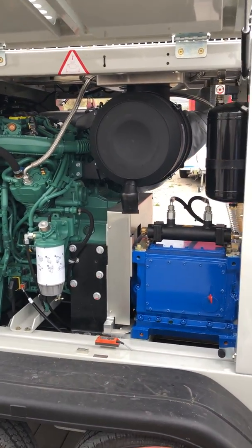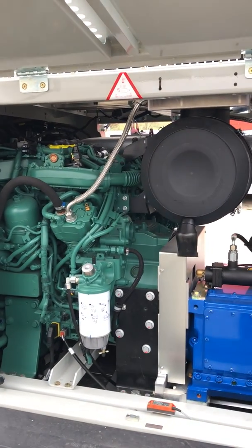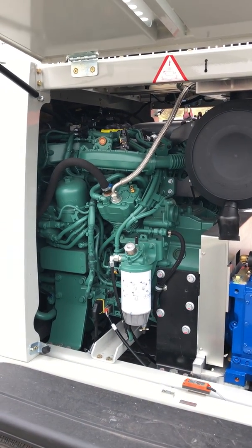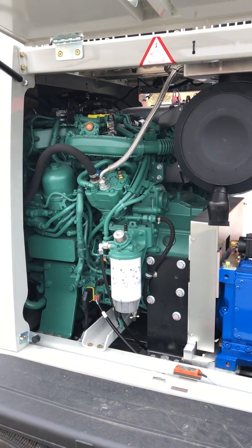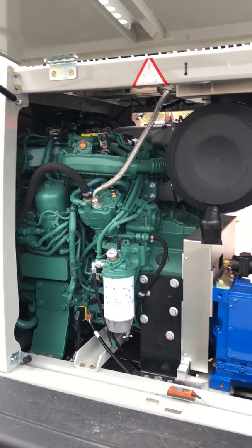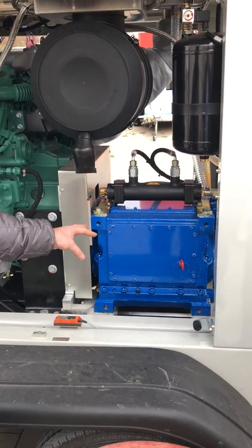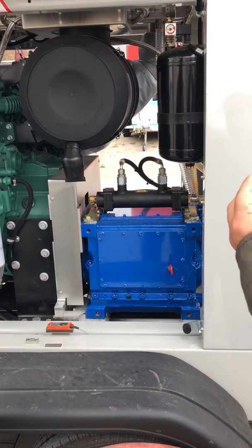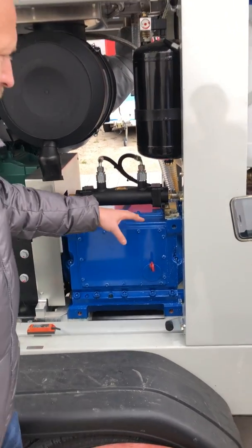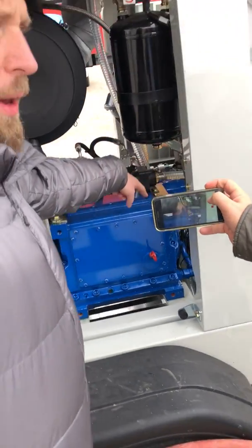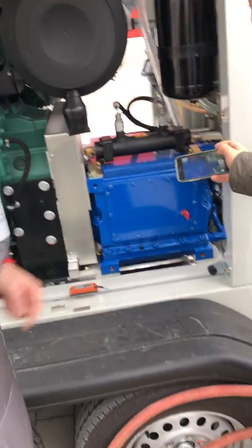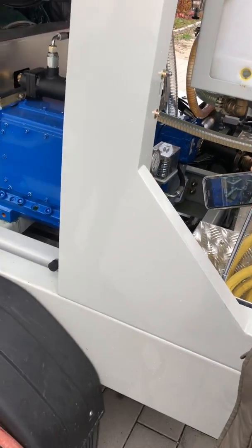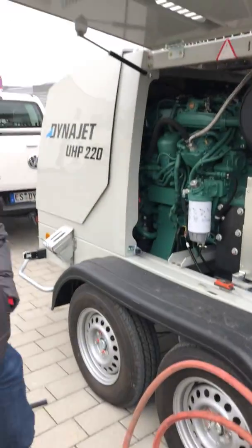So that's the engine. It's a 4-cylinder engine, 5.8 liters displacement, I think. We have a direct coupling to the pump, a soft coupling. On the pump we have a little oil pump. We have pressurized oil to cool and to grease the pump while it's running. We have a sensor in the pump for the temperature and a sensor for the oil pressure.